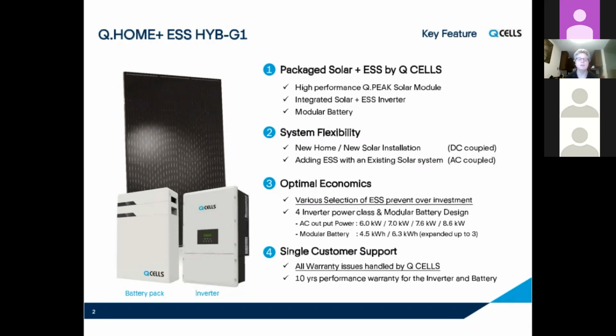So what we decided to do, and I'll show this in a separate slide, connecting three of these 4.5 kilowatt hour or three of these 6.3 kilowatt hour batteries is going to get you to a place where this inverter will fit 7,500 watts onto each backup load panel. So when someone asks what this doesn't do, it doesn't do 50 and 60 amp loads at this time.